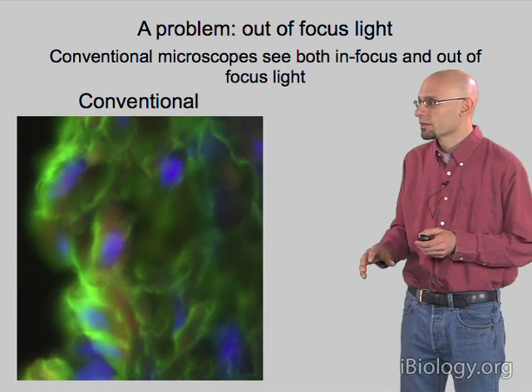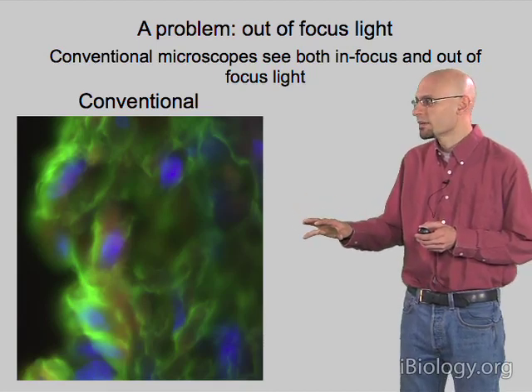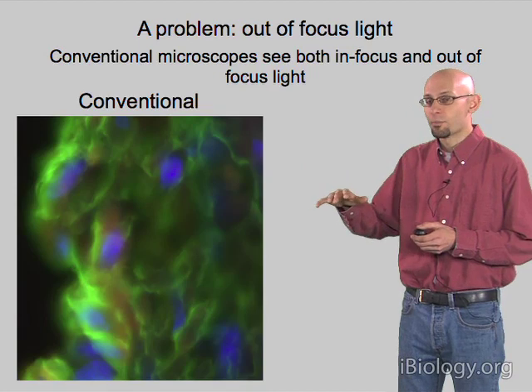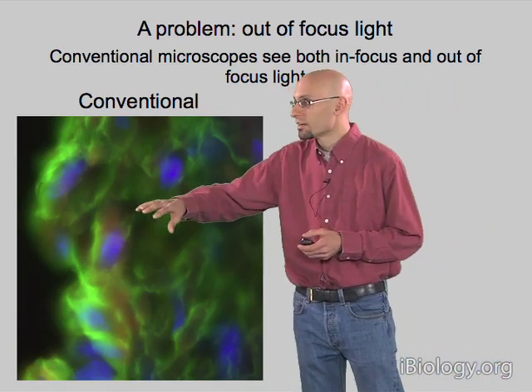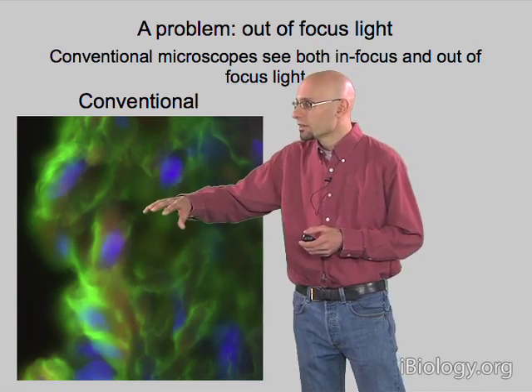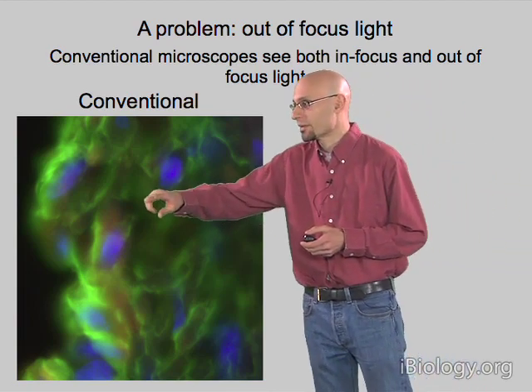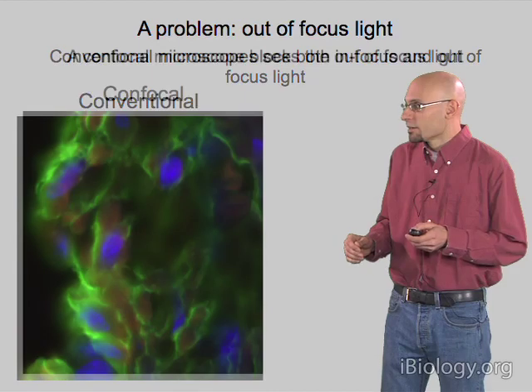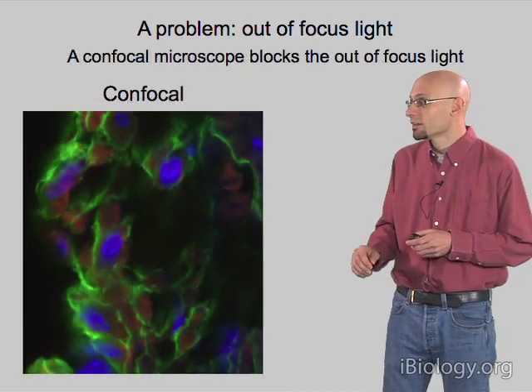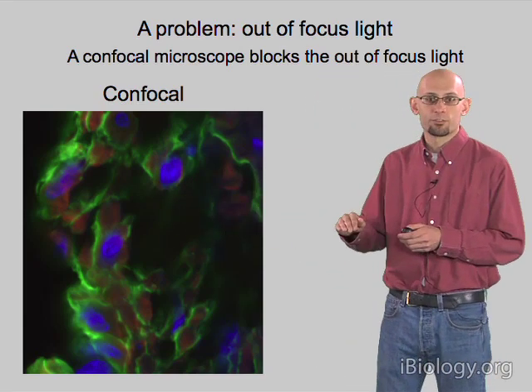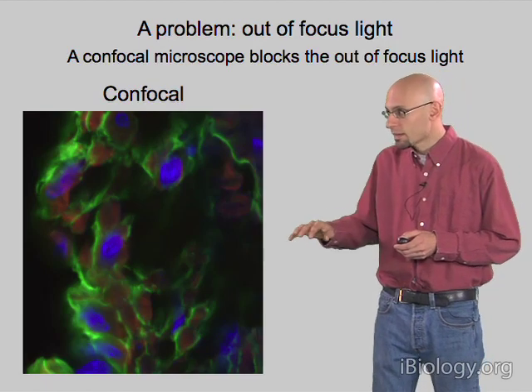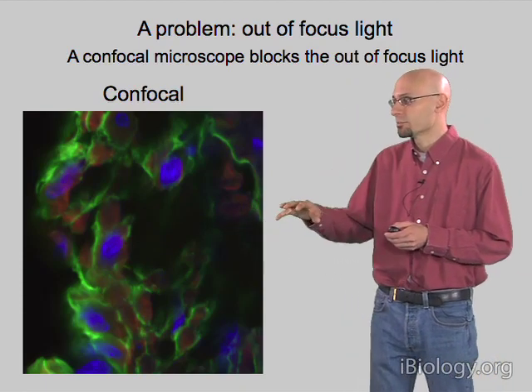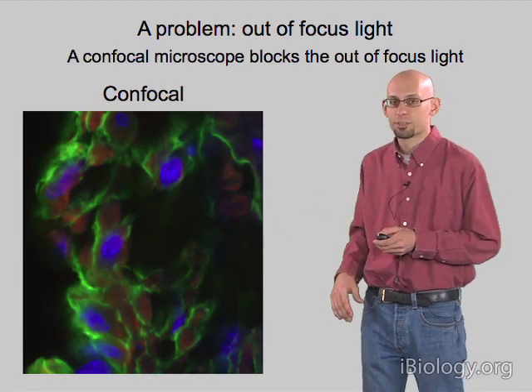The challenge is that a conventional wide-field microscope sees both the in-focus information and light that comes from above and below — from other regions in the sample that aren't in focus. You can see in this conventional image of mouse tissue there's a lot of blurry, fuzzy, out-of-focus light overlaid on the sharp edges. If we use a confocal microscope, which blocks that out-of-focus light, the image gets much sharper and crisper, because we're only seeing the in-focus information.